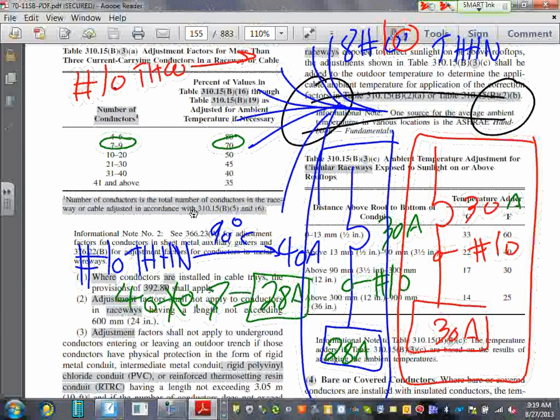But Derek, because we're using THW, what's the insulation for THW? 75 degree. How much current can that conductor carry under 75 degree? Thank you, 35. And can I go to the 90? No, because I'm goofy and I decided to use THW, okay? Now you do the math on 35 this time. 35 multiplied by 0.7. What would that give you, please? 24.5.